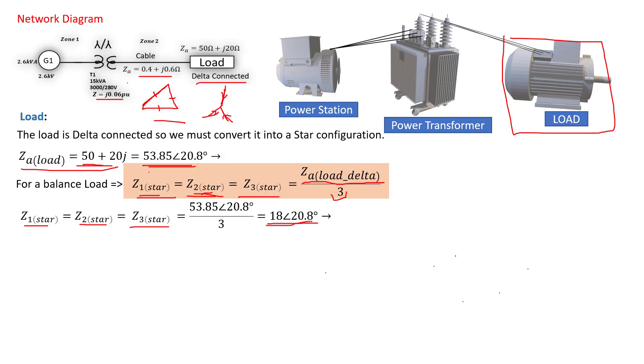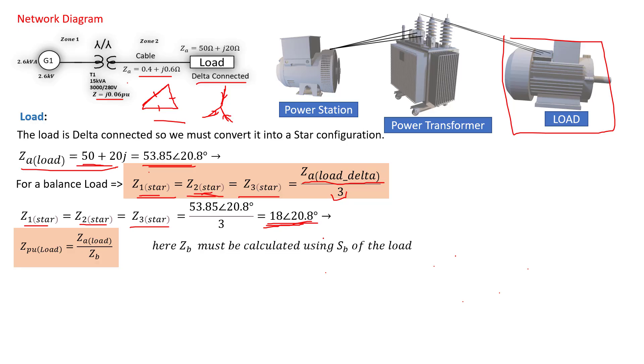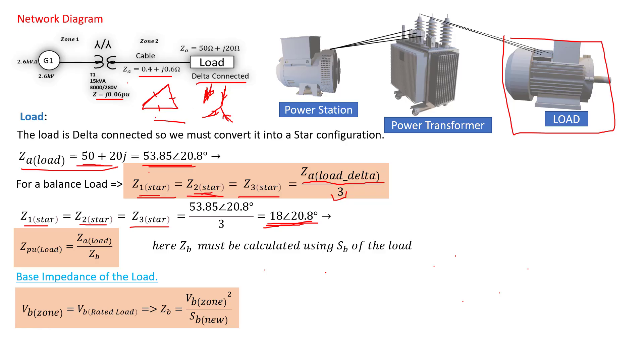Each star point now has an actual impedance of 18 ohm at an angle of 20.8 degrees. Moving on, the next thing is to calculate Z per unit. The formula is Z per unit equals Z actual divided by Z base. Z base must be calculated using S_B of the load, but because S_B of the load is not given — the motor nameplate would normally give the rated apparent power — we're going to use the rated S_B for the entire network, which is S_B new.